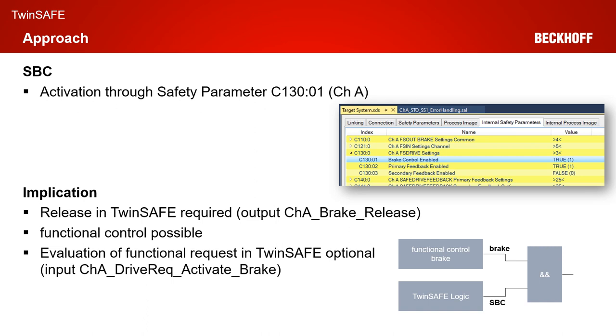You also have the corresponding signal from the functional request within TwinSafe available, which is called channel A drive request activate brake in the internal process image. But you don't have to handle it within the TwinSafe system, because after the TwinSafe logic is evaluated and the SBC signal from TwinSafe is set or not set, it is automatically evaluated in combination with the functional control of the brake. So you can use the functional brake independently from TwinSafe as long as TwinSafe acknowledges your brake control — as long as SBC is 1, for example, independent from the cycle time of the TwinSafe logic.